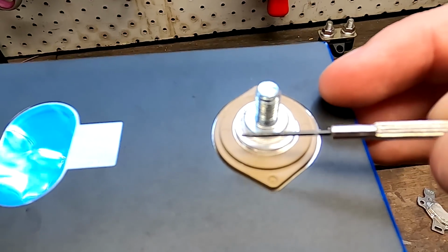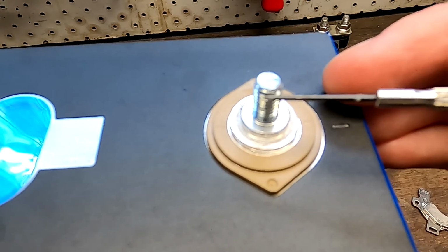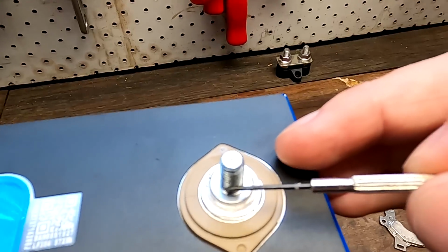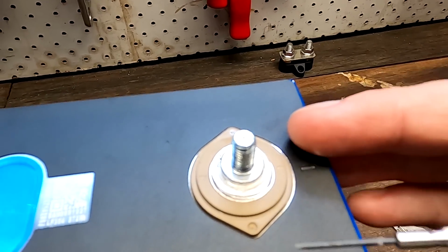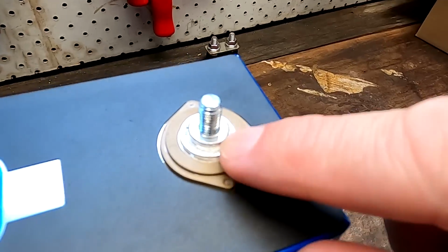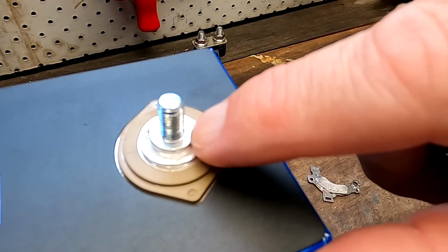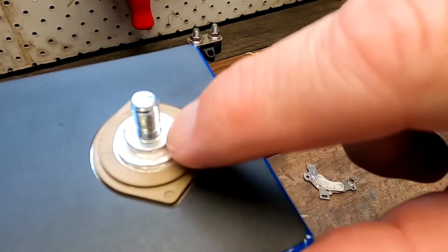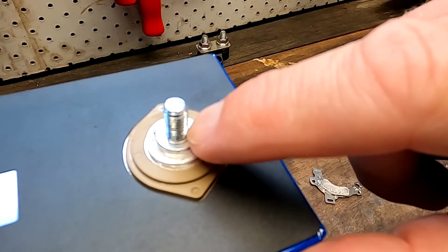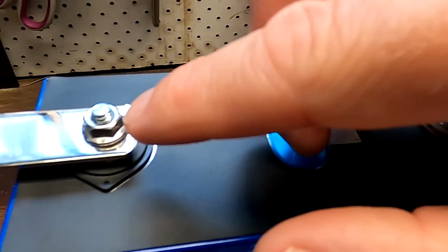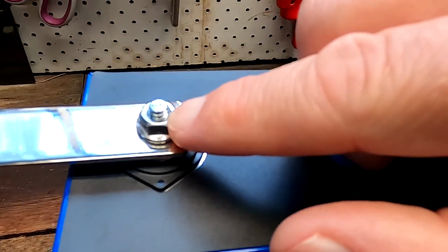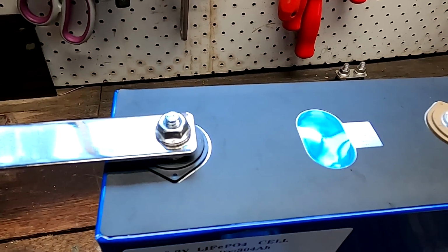A very small amount will use the path of higher resistance as well, and actually flows the way you suggested in your comments. But because of the very high resistance, I think this is less than 5%. So 95% of the current will be coming directly from this ring terminal to the bus bar directly, without going through the stud and then taking the detour through the nut onto the bus bar again from the top.